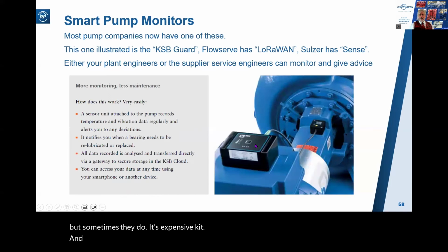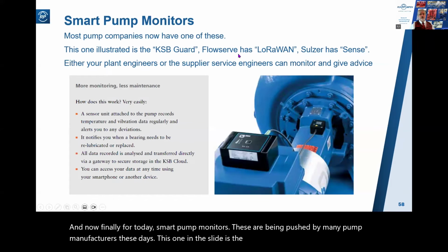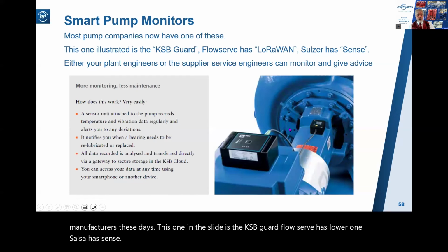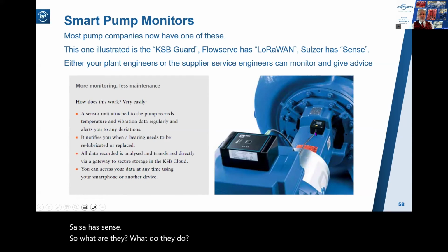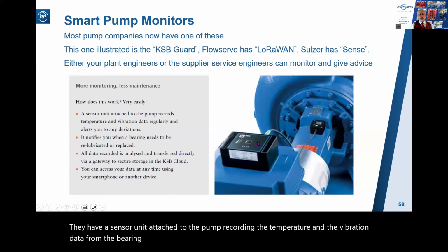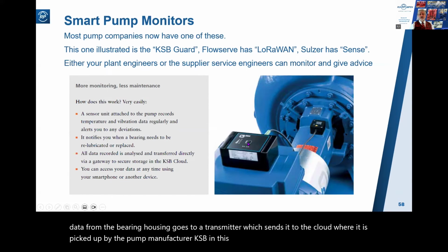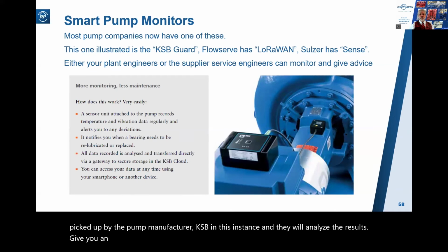And now finally for today, smart pump monitors. These are being pushed by many pump manufacturers these days. This one in the slide is the KSB Guard. Flowserve has LoRaWAN. Sulzer has Sense. So what are they? What do they do? They have a sensor unit attached to the pump, recording the temperature and the vibration data from the bearing housing, goes to a transmitter, which sends it to the cloud, where it is picked up by the pump manufacturer, KSB in this instance, and they will analyze the results and give you an alert if they think you need to do some maintenance.